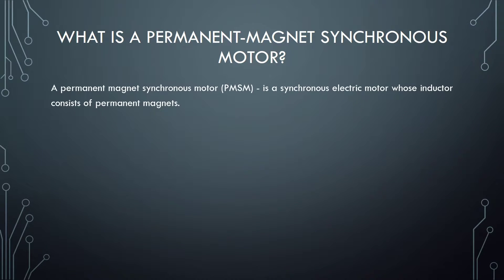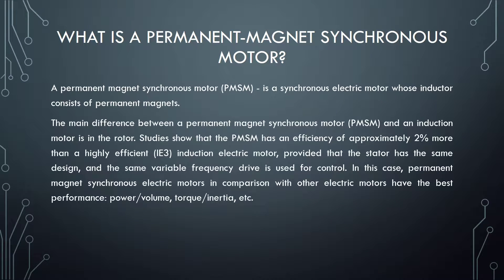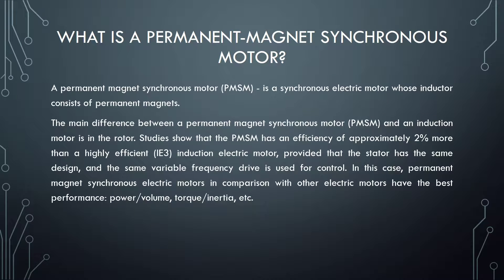Permanent Magnet Synchronous Motor, or PMSM, is a synchronous electric motor whose inductor consists of permanent magnets. The main difference between PMSM and an induction motor is in the rotor. Studies show that PMSM has an efficiency of approximately 2% more than a highly efficient induction electric motor, provided that the stator has the same design and the same variable frequency drive is used for control.